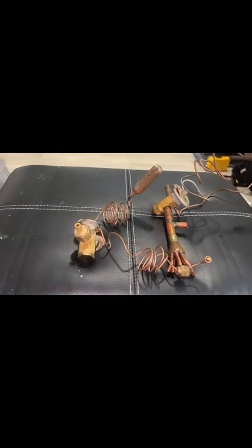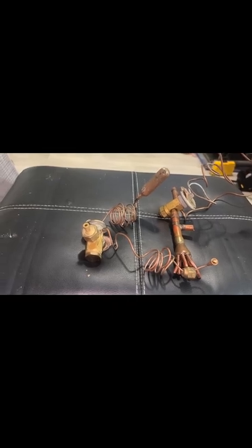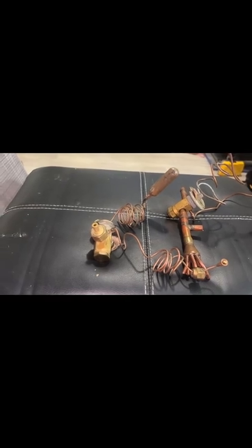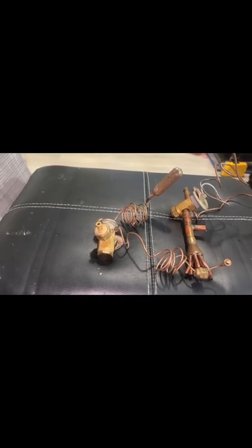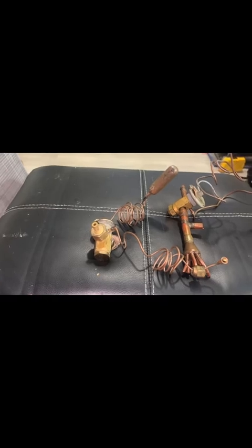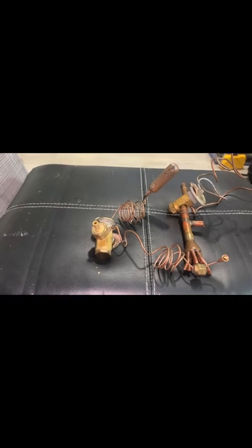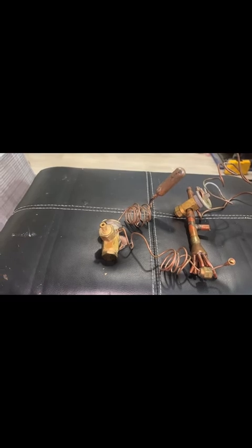It is important to note that pistons and TXVs are not exclusive to either straight cool or heat pump systems and can be installed on both, provided the correct type of application is being used. The key difference lies in how they accommodate the reverse flow of refrigerant when dealing with a heat pump system. So for a piston, pistons are commonly found in residential straight cooling and heat pump systems. For your straight cool systems, a single fixed orifice is installed in the indoor evaporator coil to meter the refrigerant flow during the cooling cycle.